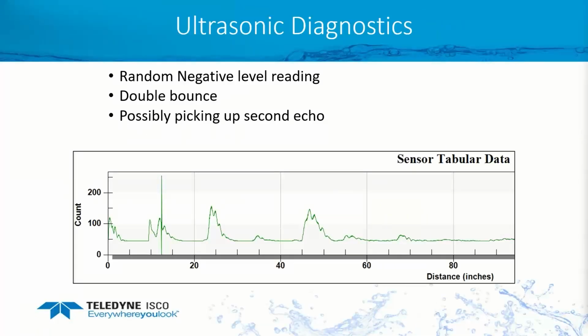Other things you may notice by looking at your diagnostics is that on your level readings, if all of a sudden you start finding that your readings are dropping in half, or maybe even going negative, one thing you may find is that you could be receiving a double echo. What happens is that the ultrasonic sensor transmits a signal, it bounces off the surface, and comes back. Usually, like right here at around 25 inches, it tells me it's 25 inches away from the sensor, and that's my level reading. But on occasion, you may find that an ultrasonic sensor has a secondary bounce, and so it picks up this one. What this is telling us is that it thinks the level is roughly 50 inches away from the surface, thus giving us a negative level.